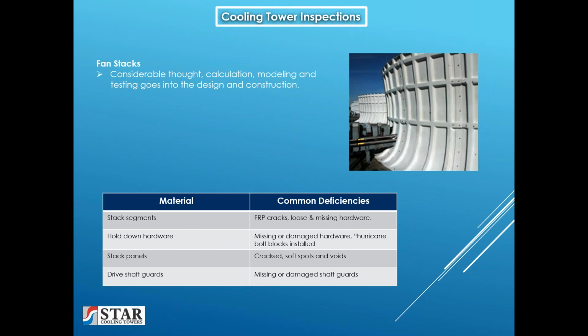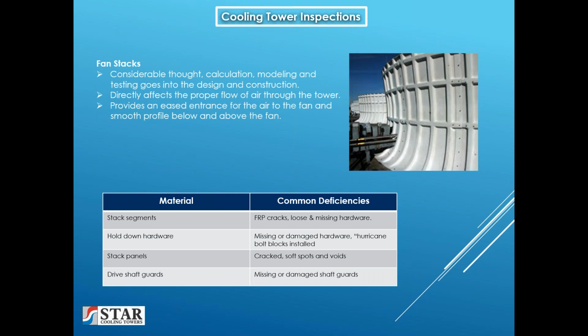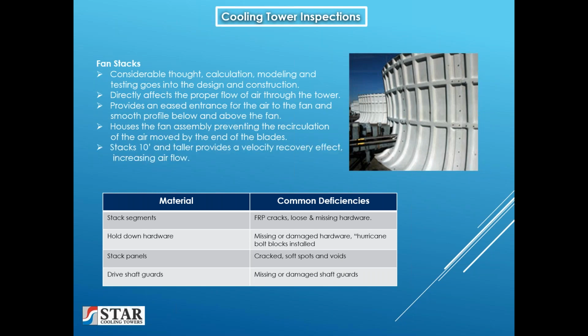The fan stacks: considerable thought and calculation, modeling, and testing goes into the design and construction of a fan stack. It directly affects the proper flow of air through the tower, provides an eased entrance for the air to the fan, and a smooth profile below and above the fan. It houses the fan assembly, preventing the recirculation of air moved by the end of the blades. Stacks 10 foot and taller provide a velocity recovery effect, increasing airflow.